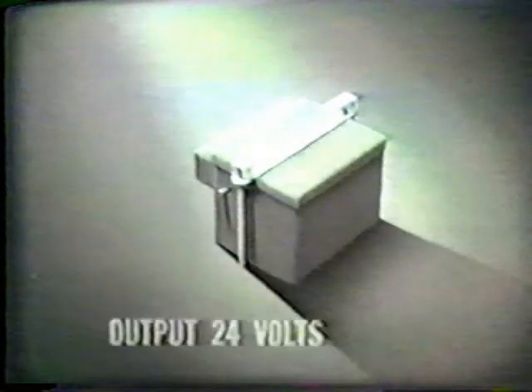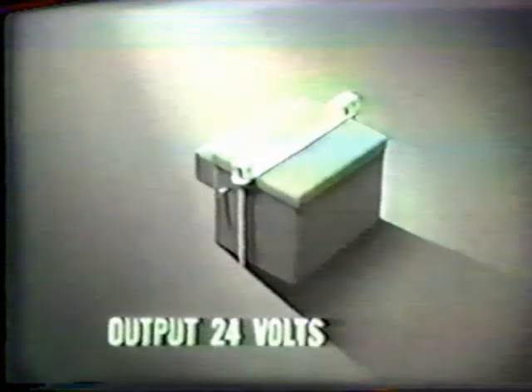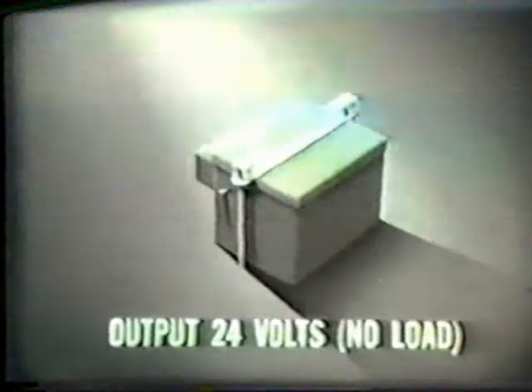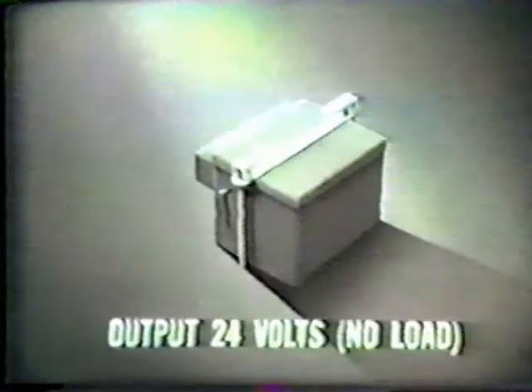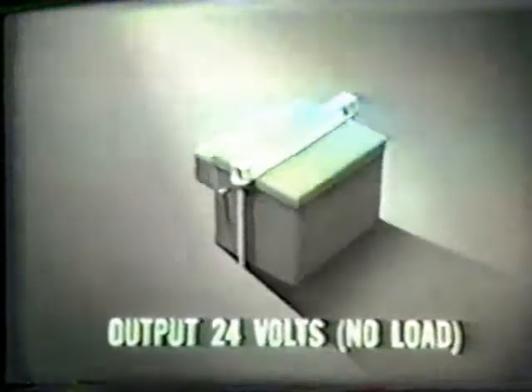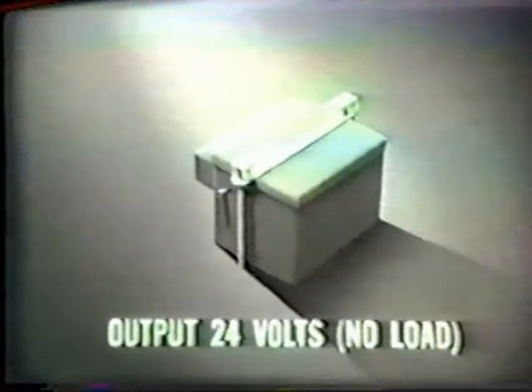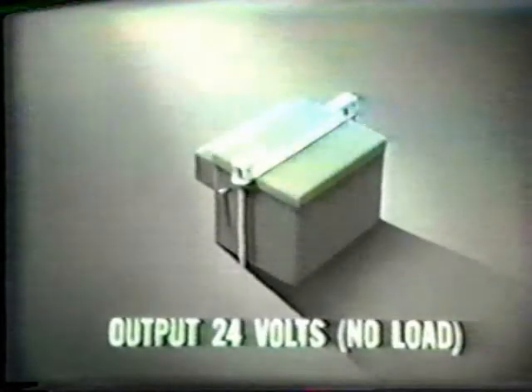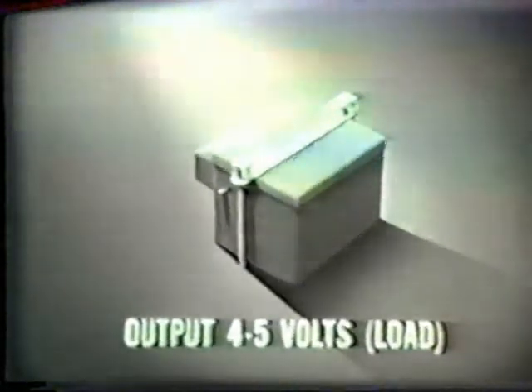Our third common type of electrical trouble, low power, differs from the other two. Low power causes motors to run slowly and relays to chatter and not close firmly. Lights may be dim. The trouble will be in the power supply. The important thing to remember is that the battery may put out 24 volts when it is tested under no-load conditions. The trouble, low battery charge, only shows up when it is tested while connected to power-consuming units. You will find that output may be only 4 or 5 volts when under a load. The solution is to charge or replace the battery.